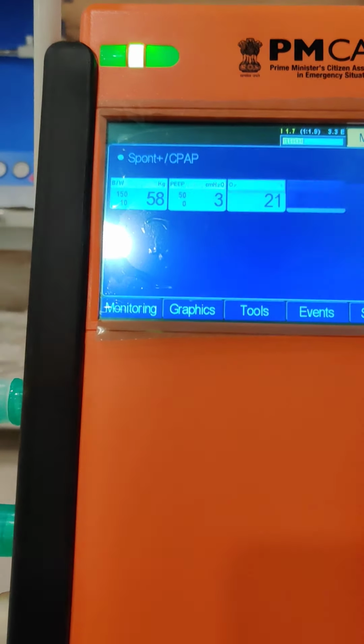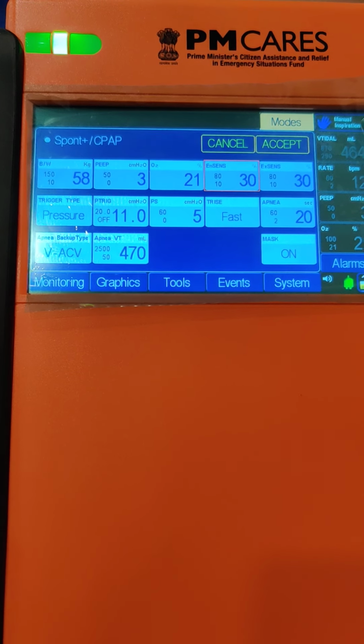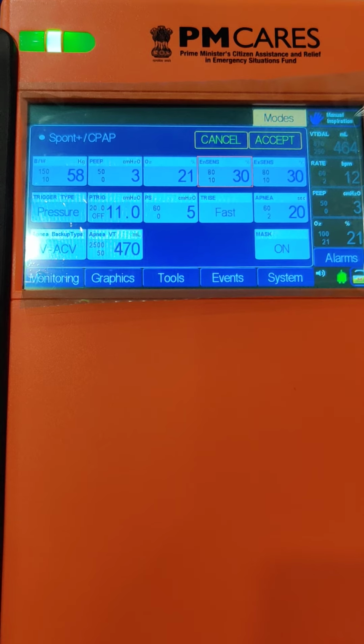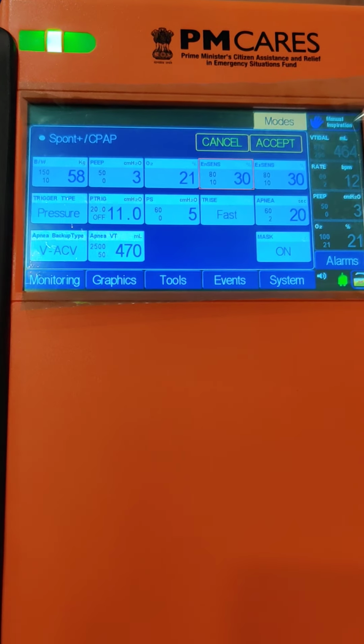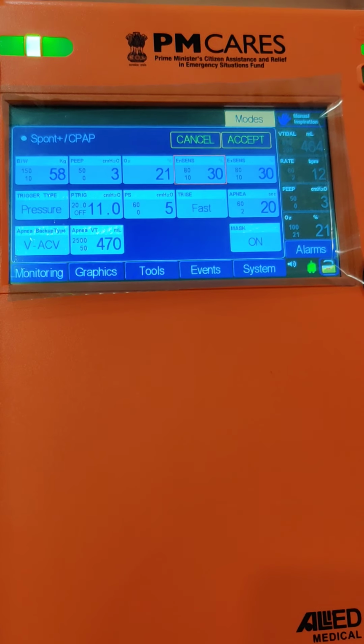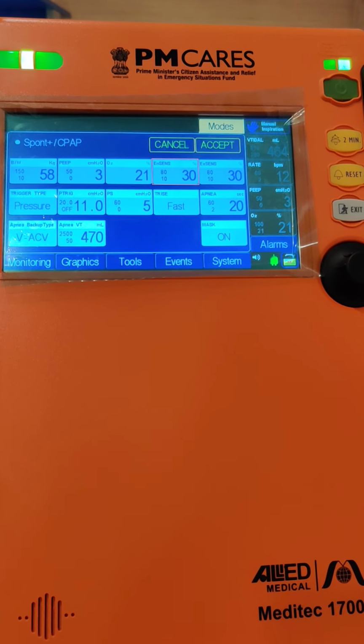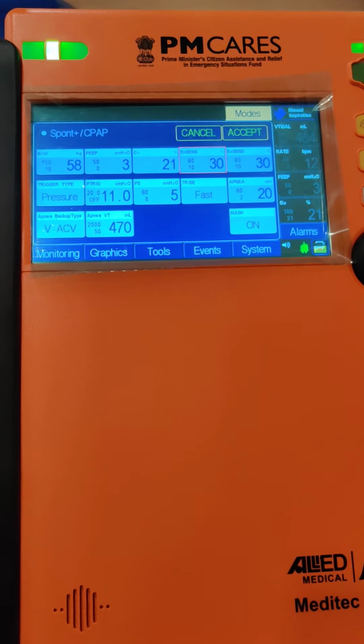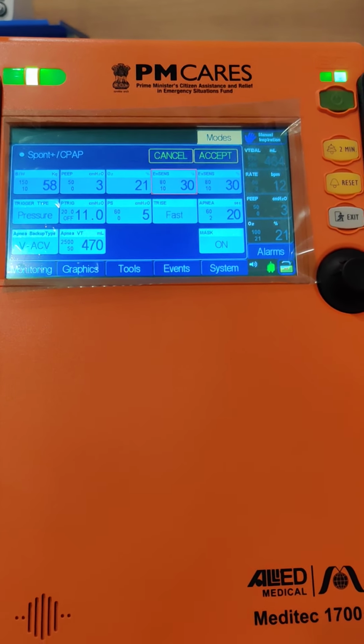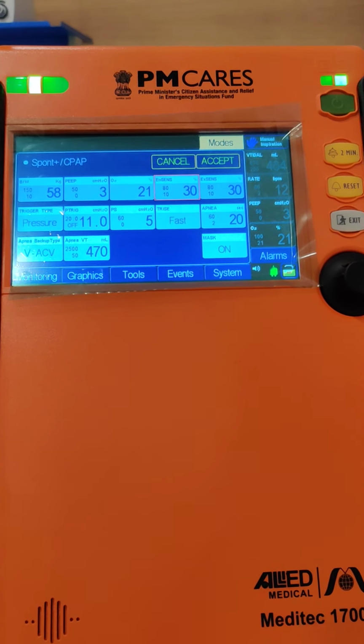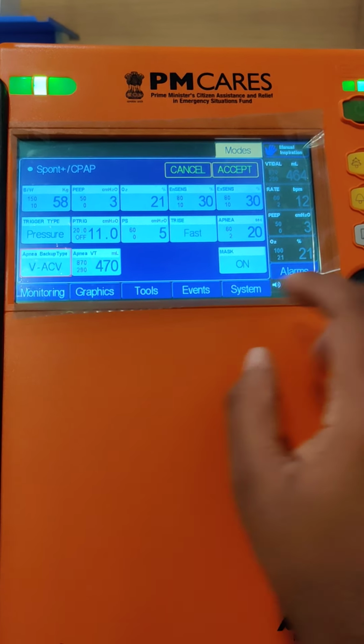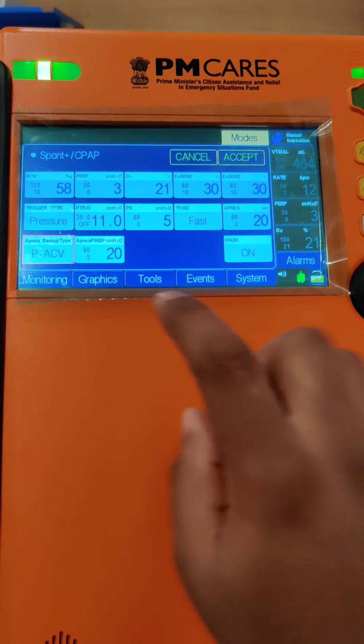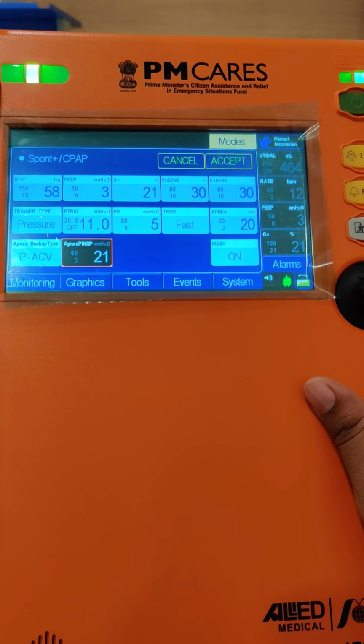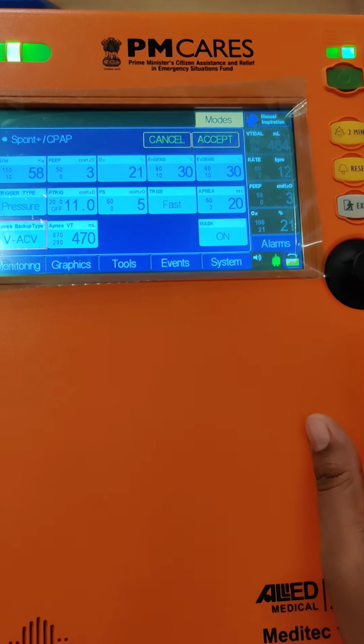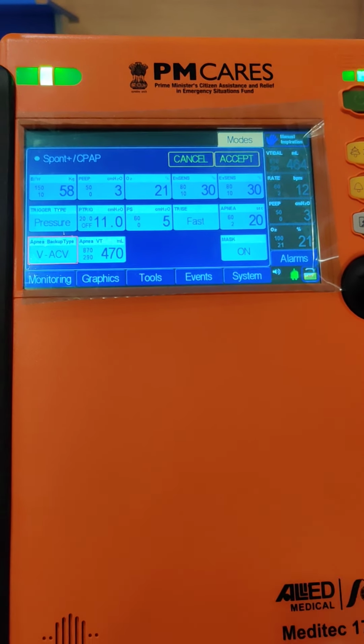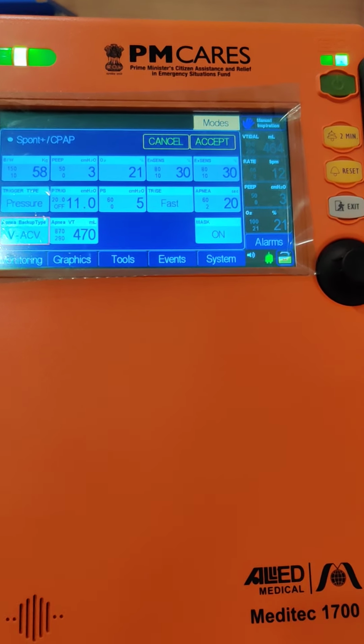Then we have this spontaneous CPAP mode of ventilation over here. Here you just have to set the pressure support of the patient when the patient is breathing spontaneously, and along with this we are giving the apnea backup ventilation also. So if the patient goes into apnea, or there is some problem and he is not breathing spontaneously, then the ventilator will first show the apnea alarm, and then it automatically goes to the apnea backup ventilation, that is either in volume or in pressure. So in pressure you have to set the apnea inspiratory pressure, and in volume you have to set the apnea tidal volume.